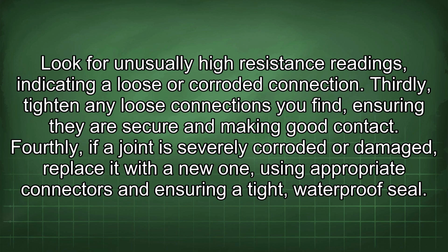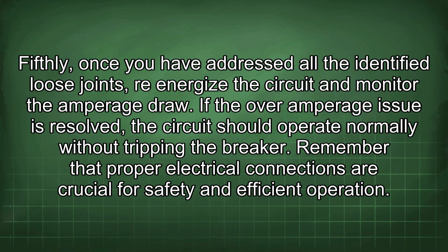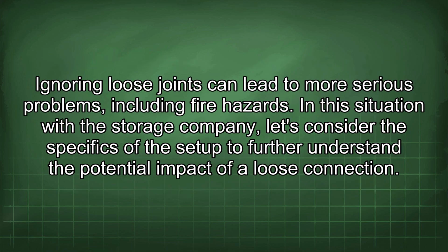Fourthly, if a joint is severely corroded or damaged, replace it with a new one, using appropriate connectors and ensuring a tight, waterproof seal. Fifthly, once you have addressed all the identified loose joints, re-energize the circuit and monitor the amperage draw. If the overamperage issue is resolved, the circuit should operate normally without tripping the breaker. Remember that proper electrical connections are crucial for safety and efficient operation. Ignoring loose joints can lead to more serious problems, including fire hazards.